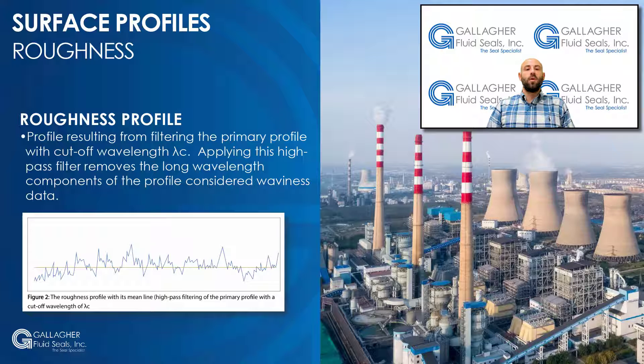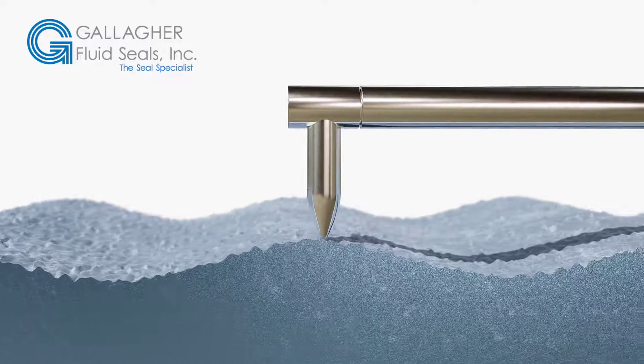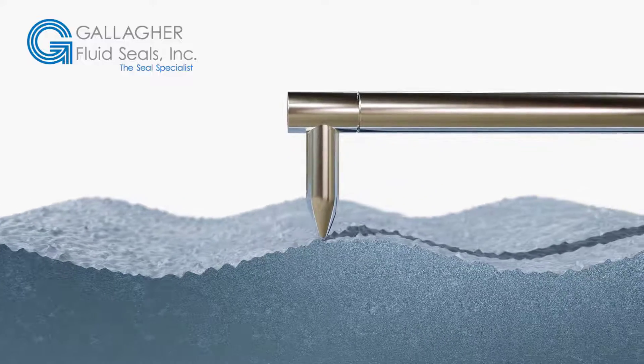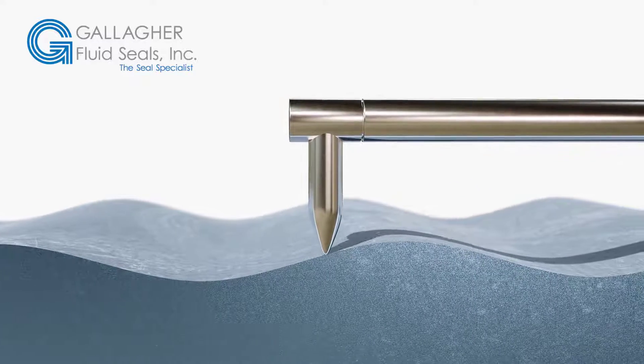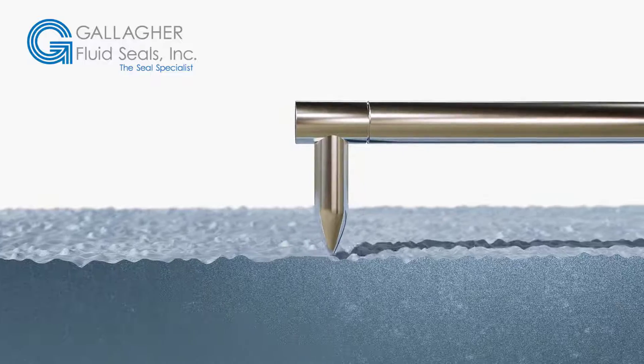The roughness profile is generated by filtering the primary profile with cutoff wavelength lambda c. Applying this high-pass filter removes the long wavelength components of the profile considered waviness data. The roughness profile, as seen in the below depiction, is the profile we are most interested in with respect to characterizing a surface that directly correlates to seal performance. Also seen in the below image is the mean line, which is established once appropriate upper and lower cutoff filters have been applied to the measured profile and is the flat reference line from which the profile deviations are quantified. In the first animation, you can see that our measured profile contains both long wavelength waviness and short wavelength roughness components. The next animation portrays the filtered waviness profile, and the final animation depicts the filtered roughness profile from our measured profile.